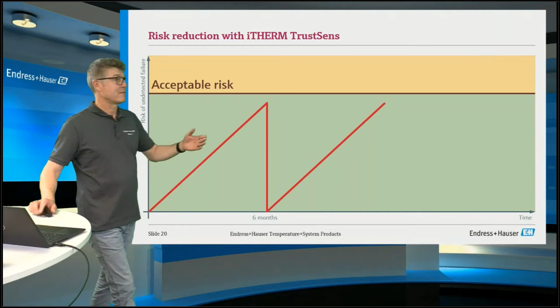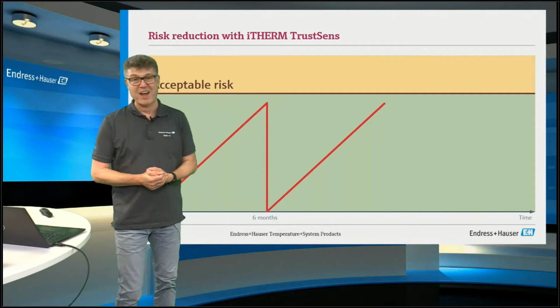Because what is done during a calibration today is you do your calibration at one moment. In the majority today, like written here, every 6 months you do a calibration. So you do it here, you hope everything is fine, and then you pray that nothing is happening in the next 6 months, which is typically true. You do the next calibration, now you are sure, all right, the instrument is still okay, so also in this period of time everything was fine too. But the fun begins here.